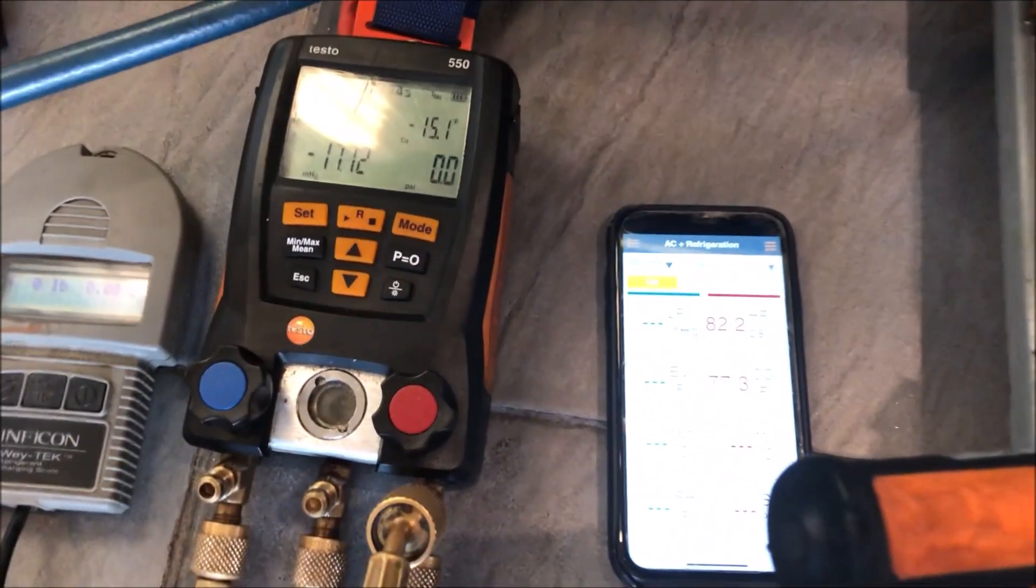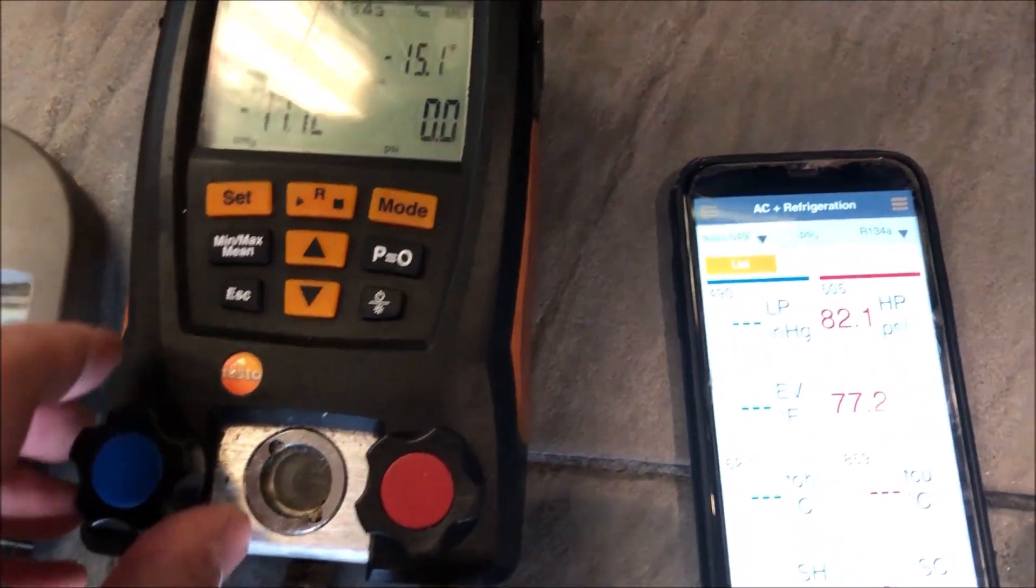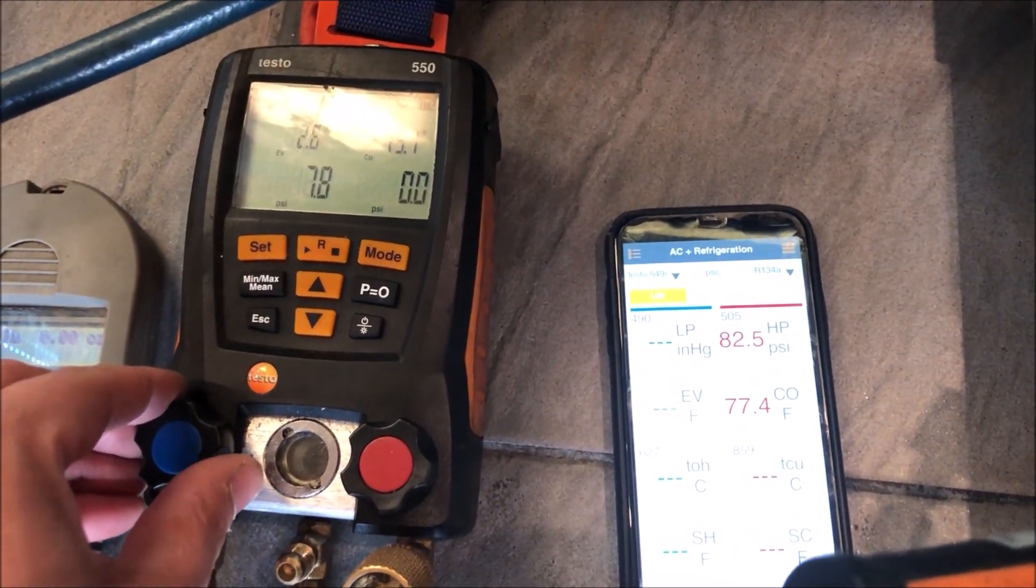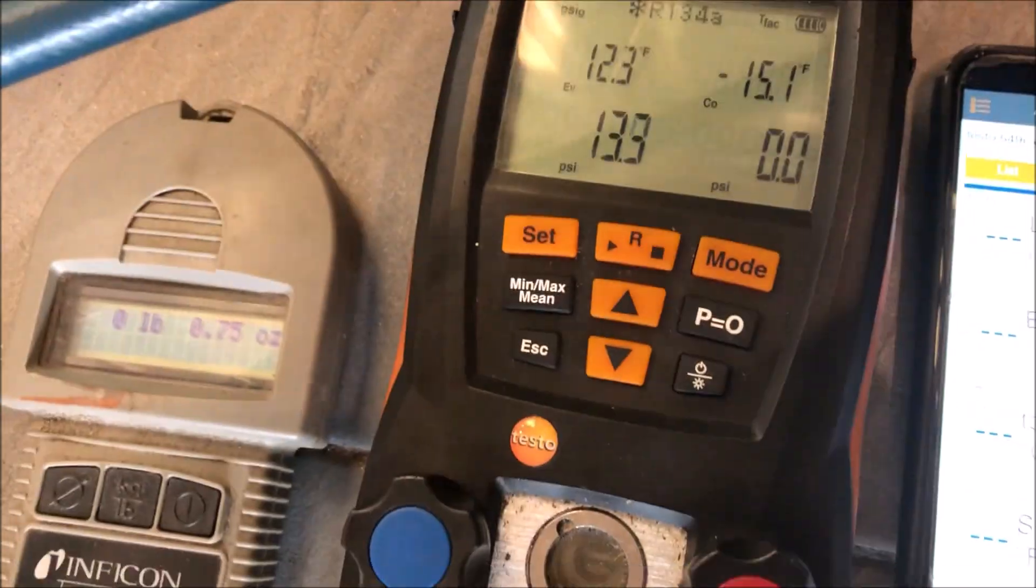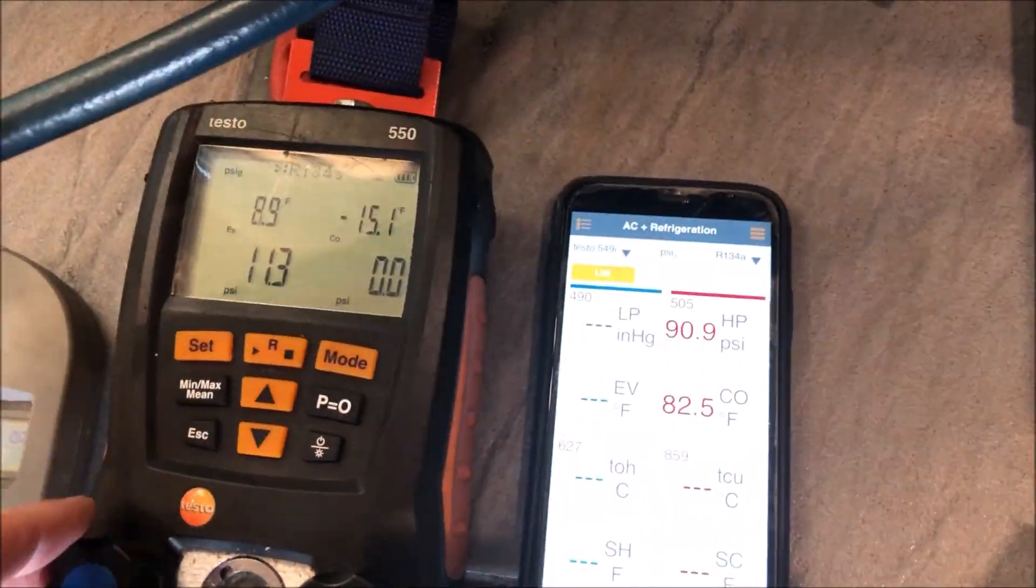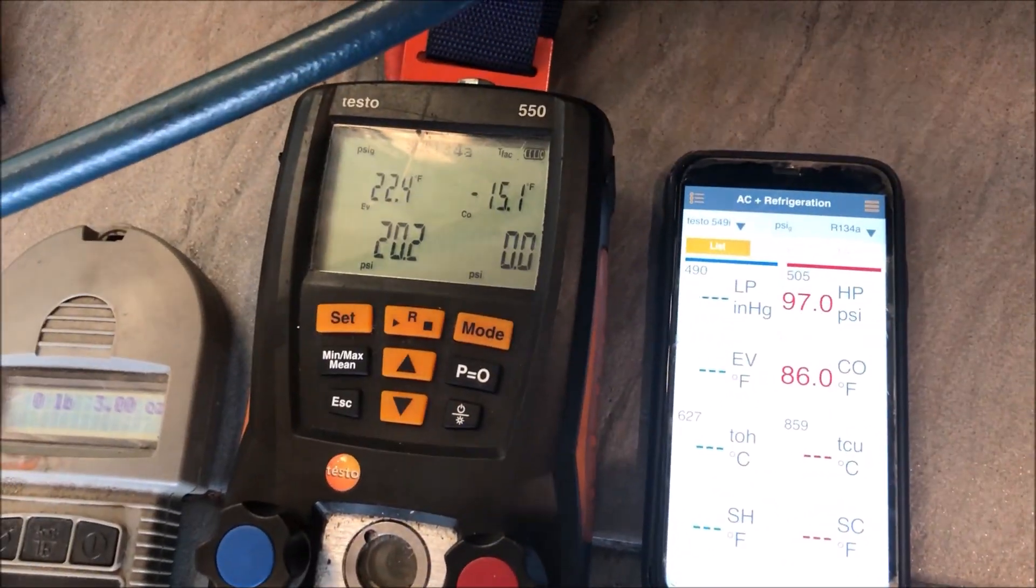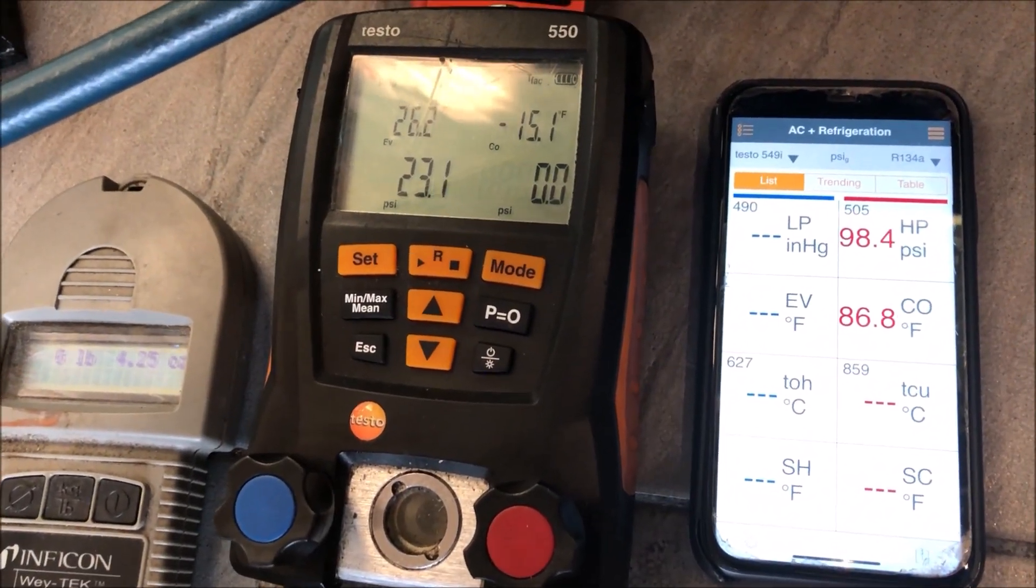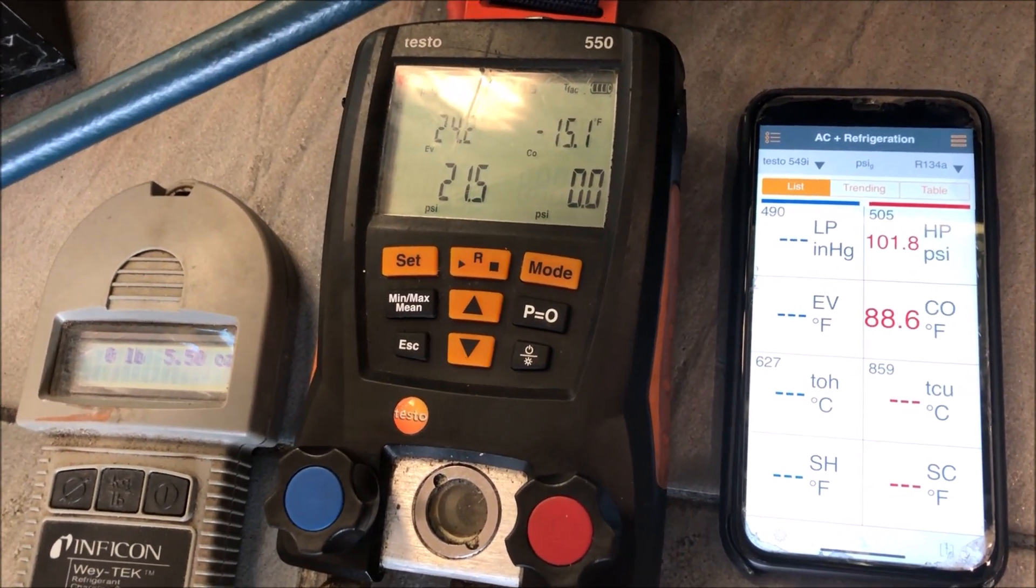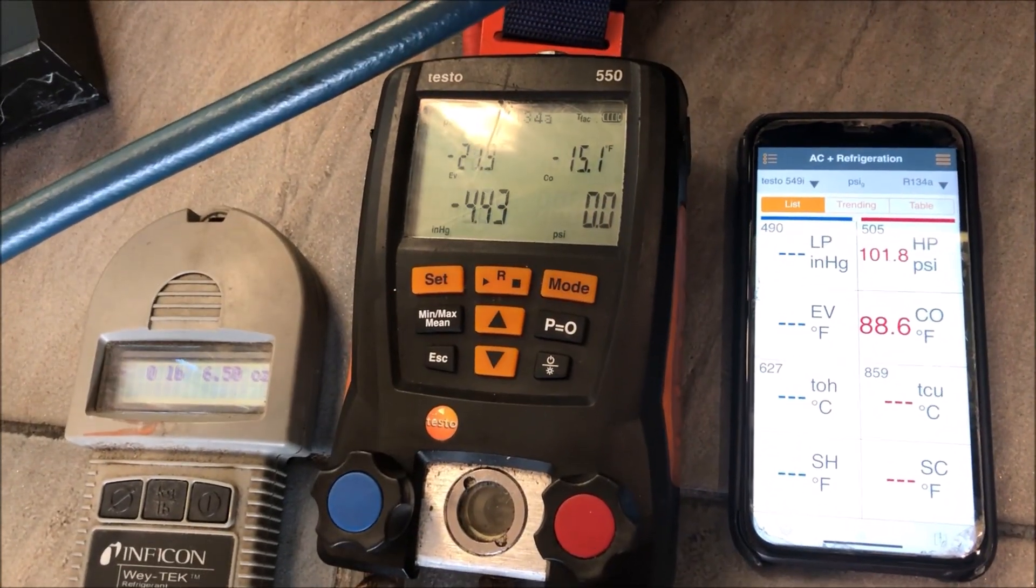Our head pressure dropped down to 69. Let's slowly throttle in some 134a. You can see our pressures are up right now, but obviously our valve on the gauges is open, so that's why. We're just gonna push in a couple ounces here and then we'll close off our gauge and let's see if the pressures drop or if they stay up.